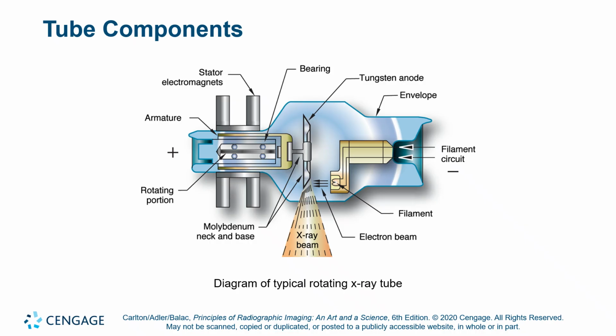So then we surround the whole thing in a capsule typically made of glass, that envelope, but not always made of glass. Some of the modern designs are using sheet metal, steel, or aluminum or alloys to build X-ray tubes. We figured out we don't have to use glass. We can use a metal envelope, and that helps with filtrating the X-rays. A particular part of the envelope is called the window. It's not labeled here, but it's where the X-ray beam is coming out. In a glass envelope, the window portion of the envelope is thinner than the rest of the envelope, so that the window and the glass envelope don't absorb as many X-rays. I don't know if that carries over to a metal envelope or not.